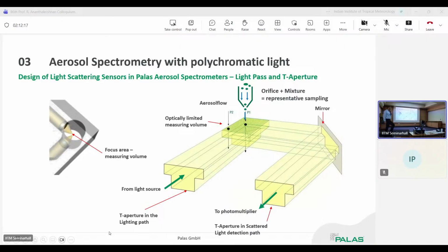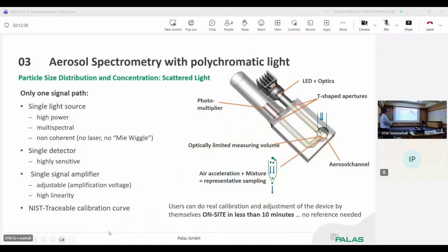We have 90 degrees light scattering. But what we do, the signal is very, very small, so we have to amplify it anyway. Yeah, with a photomultiplier. A sensitive photomultiplier, so every signal coming from here will be amplified. So if the signal is higher because particles are bigger, then we reduce the amplification. Of course, we then also raise the lower limit of recognition of particles because we cannot amplify them anymore. The signal is too small, then we cannot amplify.